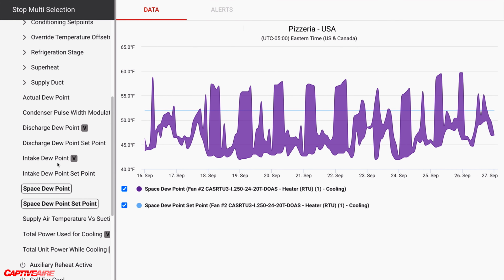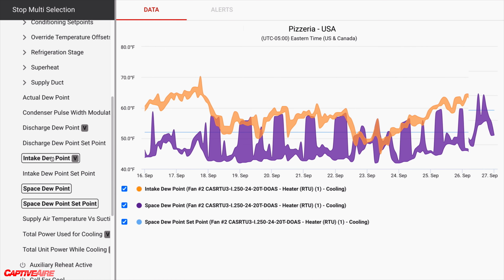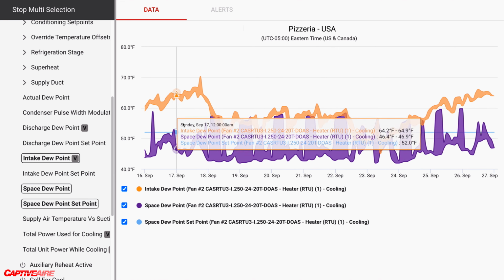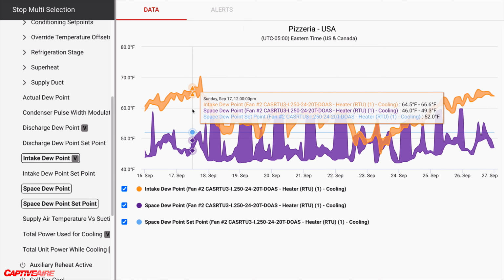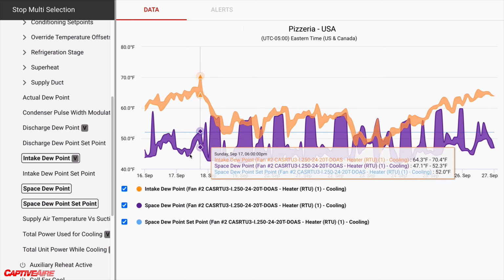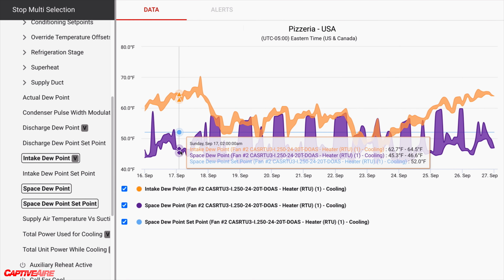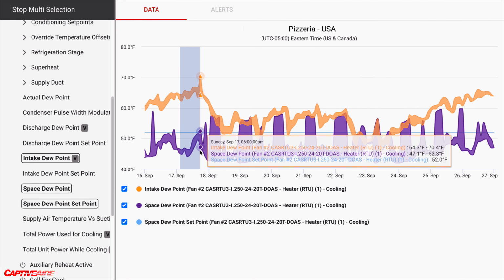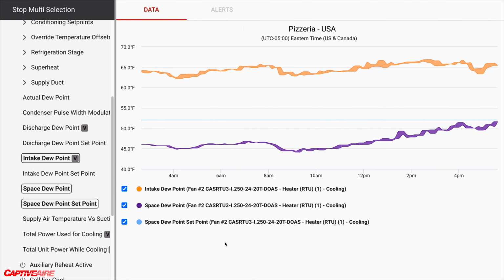So what I'll plot in here is I want to do a check to see the intake dew point to see if it's anything above that 52 set point, and then we're coming out with a space dew point in the 40s. That's because of our unit dropping that dew point of the space and essentially over dehumidifying. And that's exactly what we see here. So we have a lot of options on how we can adjust our dehumidification to react based on space conditions.